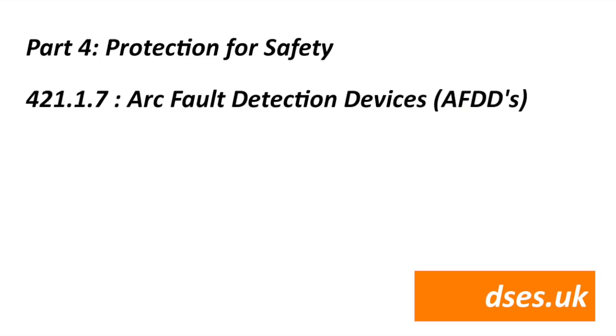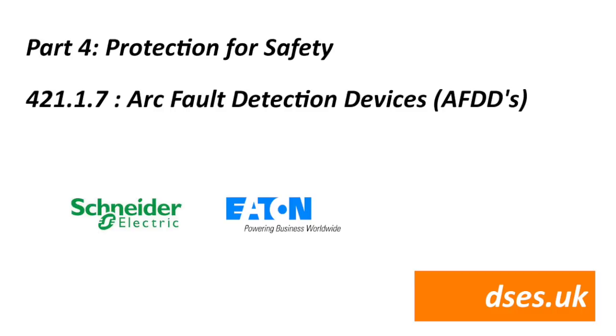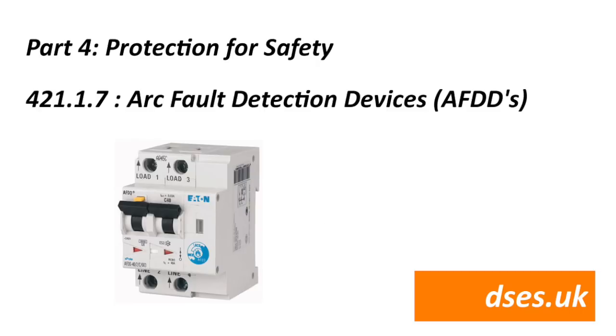18th edition slips AFDDs in as a recommendation — use them if you want — with the expectation that future revisions will make them mandatory. However, at the time of recording I see four problems. Number one: they're currently very expensive, though prices should drop with economies of scale. Number two: they're impossible to get hold of — I've been trying to get a Schneider or Eaton model but none of my usual resellers can get one. Number three: they're huge — an AFDD with RCD and MCB protection takes up three fuseways for one circuit. Consumer units of the future are going to be behemoths. Number four: if regulations ever require them in retrofit applications, I'll be pulling consumer unit replacements from my offered services.